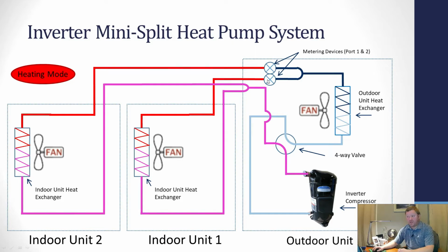Now, the expansion valve that's on the liquid line side back at the outdoor unit can throttle down and close, but it can't close 100%. It can't stack up the refrigerant all the way back through into the hot gas line. So it has to stay at least a partial way open. But even though it's closed as much as possible, you still have flow. And if you still have flow, you still have heat rejection. So you have to be really careful when you're sizing the indoor units and when you're sizing the outdoor unit, because you don't want the compressor to be too big and overshoot all of your set points.